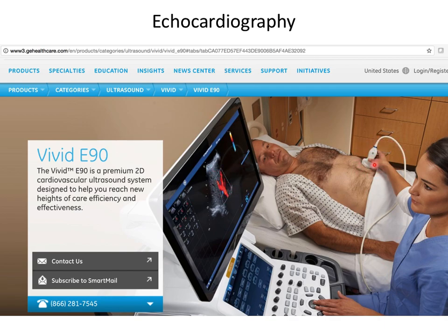This transducer sends sound waves into the patient and then listens for reflected sound waves back from the patient. So it both emits and then receives sound waves. And based on the echoes that the system hears, it constructs a picture of where those major echoes are coming from, the distance away from the transducer. And if she were to tilt this and point it up towards the heart, she would see the heart. So where you are imaging is absolutely controlled by how you point the transducer.